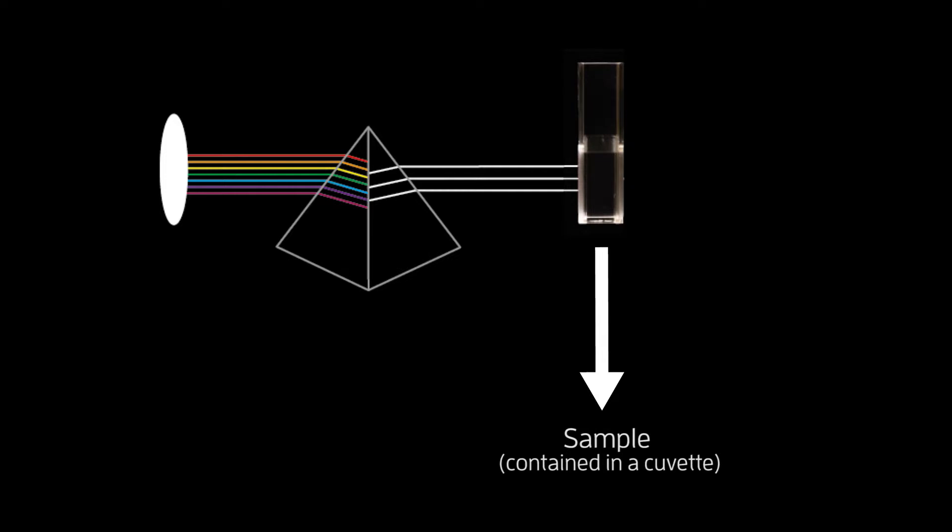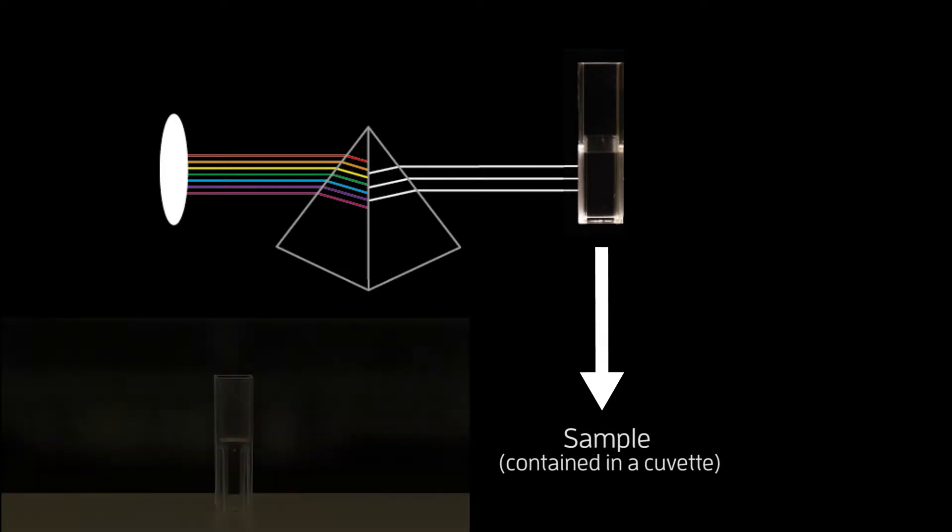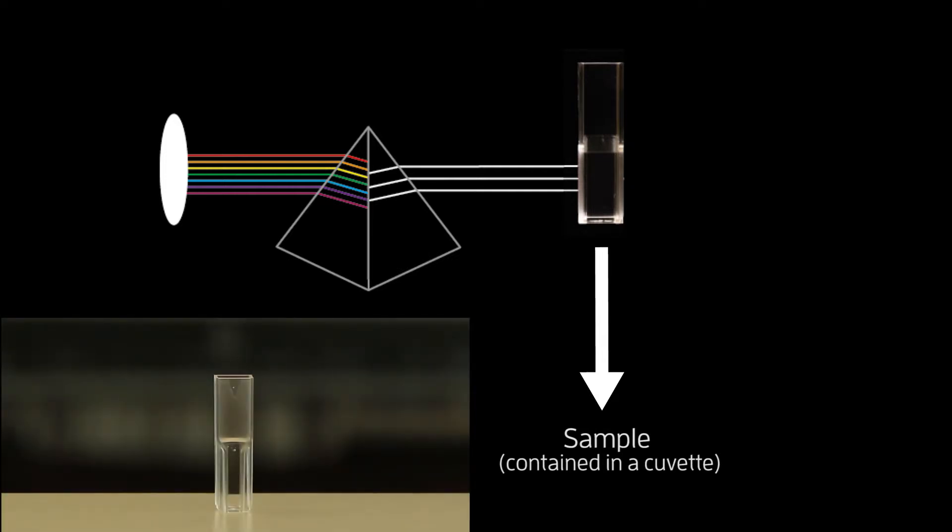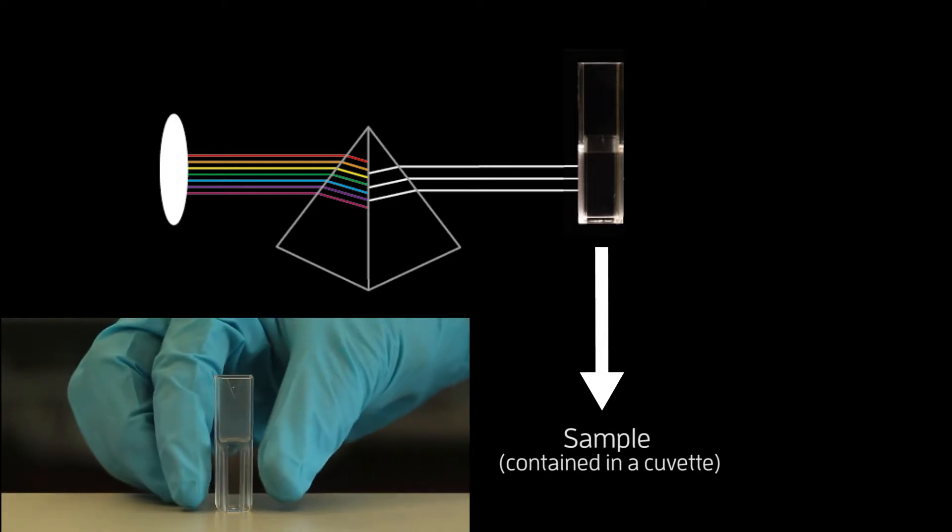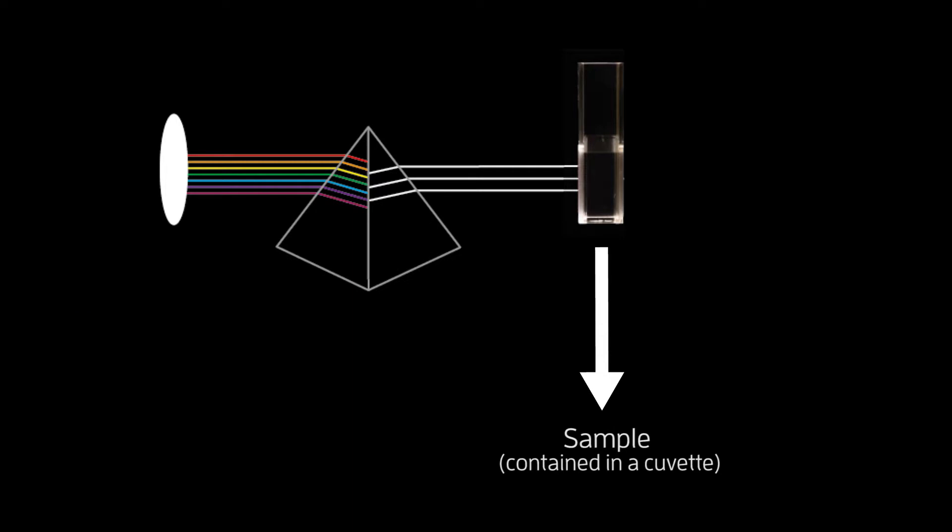Thirdly would come the sample which is contained in a cuvette. Cuvettes are small containers of known path length. They may be made of polystyrene or other plastics or in some cases quartz. You must select your cuvette carefully to prevent obstruction of wavelengths.